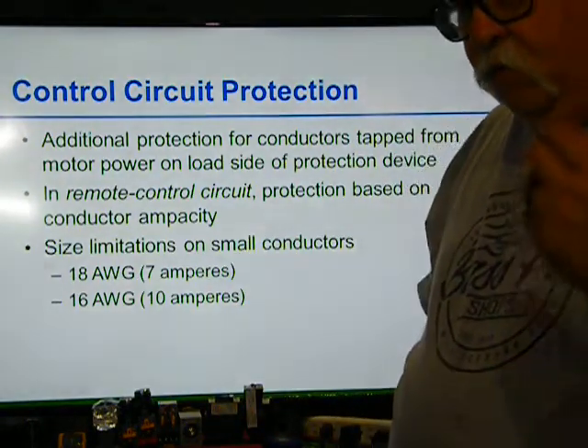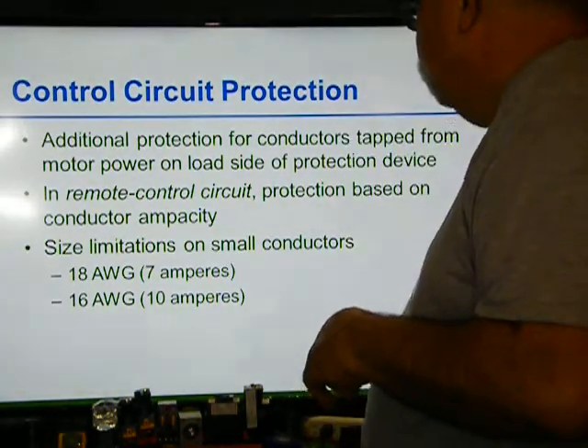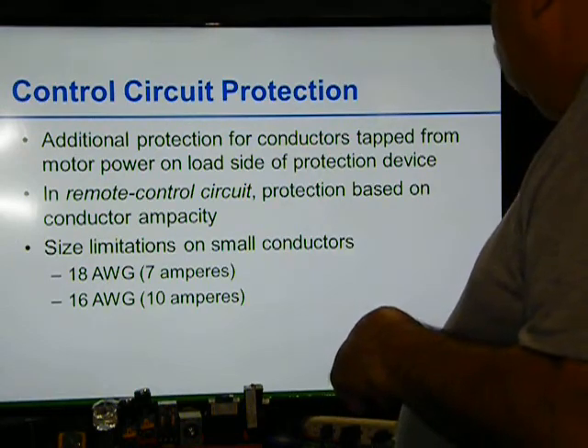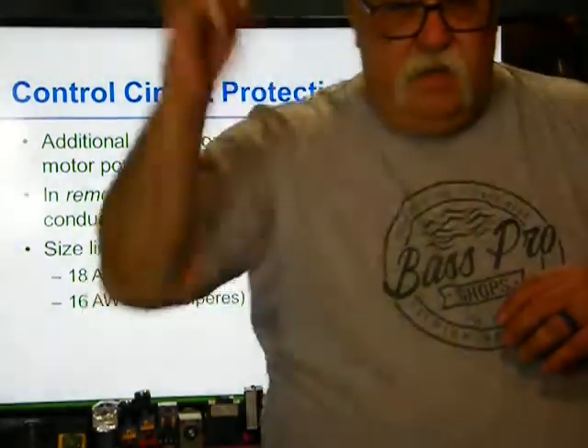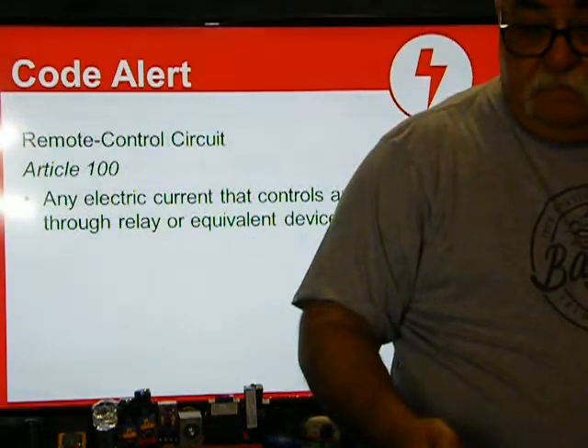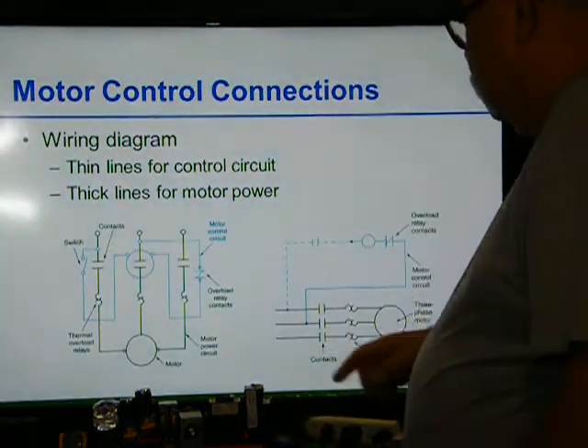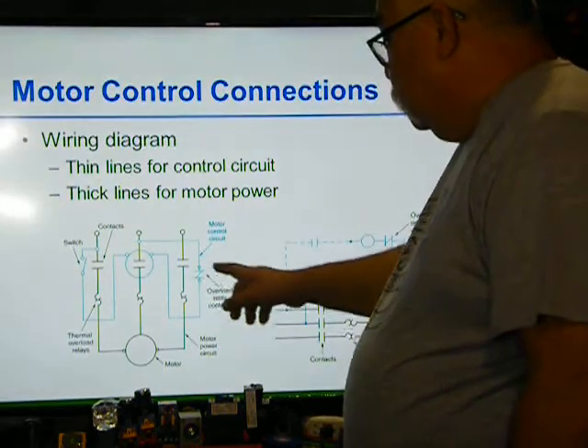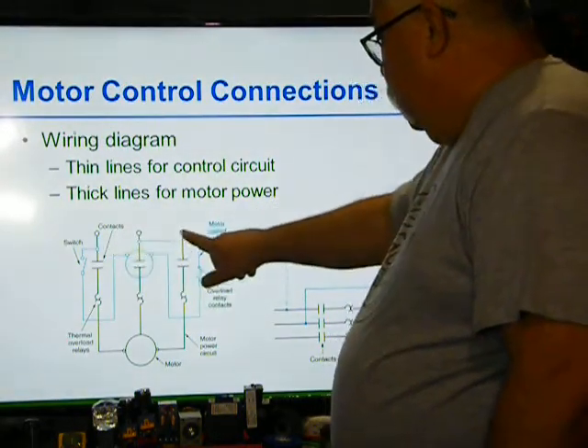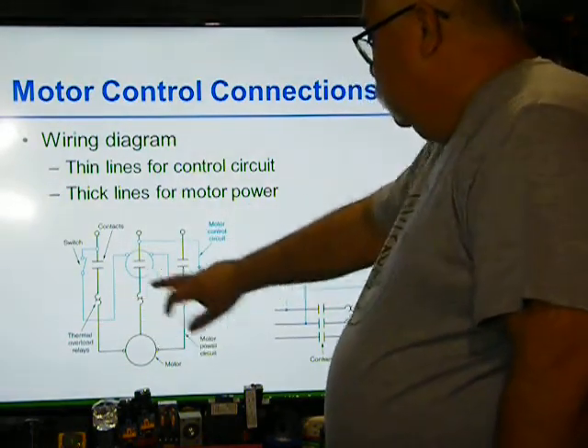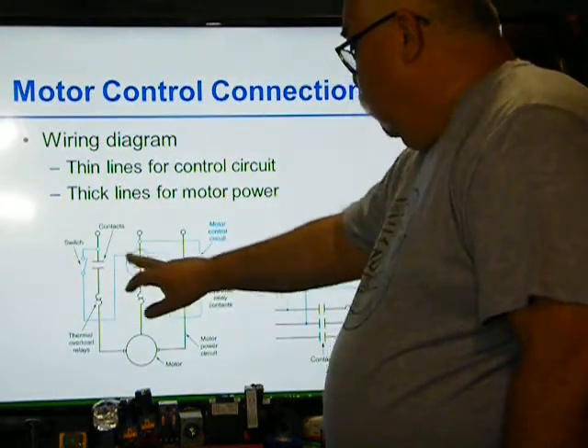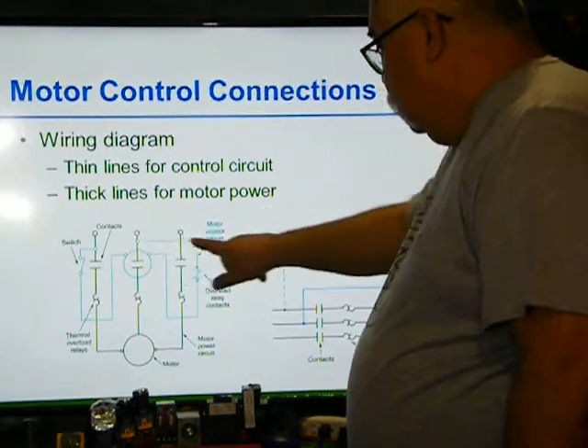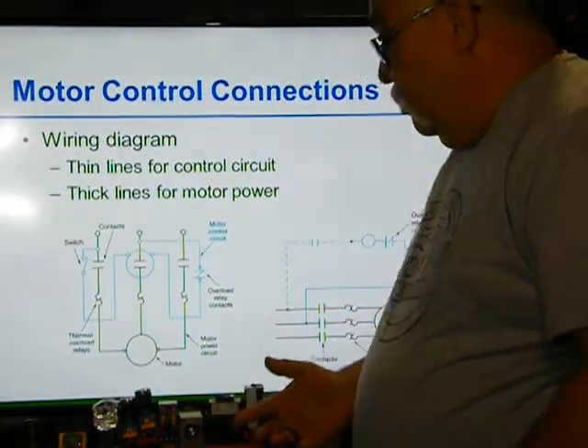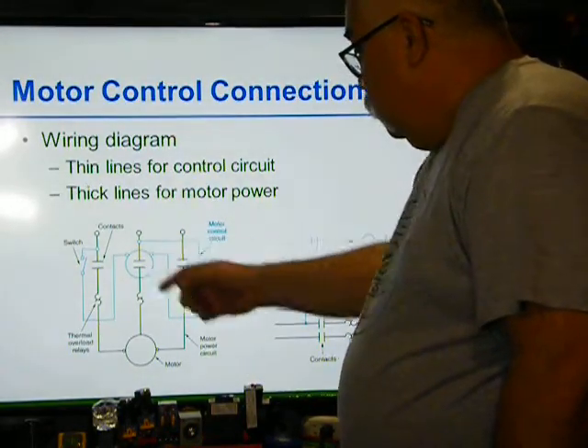Okay, that was part of the other one. So they usually use the transformer to control the circuit. Circuit protection: additional protection for conductors tapped from the motor power on the load side of a protective device. So if you have a motor, I have a circuit that comes off. Here's my power. This one is a 240 volt control circuit. Here's L1, L2, L3, here are my contacts, and here are my overloads. They're getting power off of one to come to the coil. This is the coil. And they're getting power off of another one, so this is L2. So this is going to be a 208, 220, 230, or 240 volt coil. So they're getting two. In that case, you don't have to have protection.